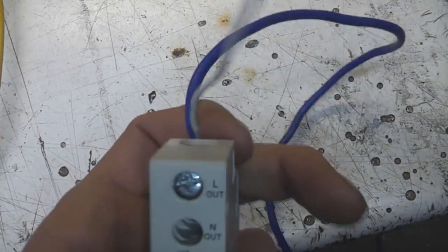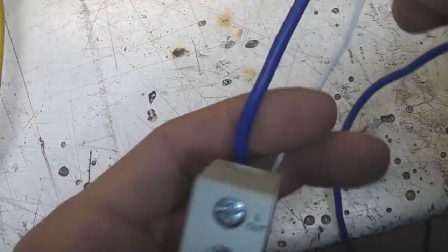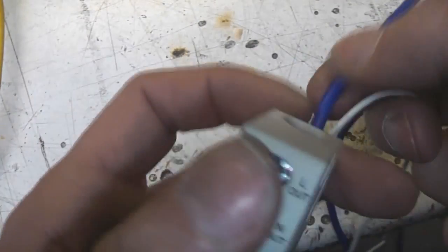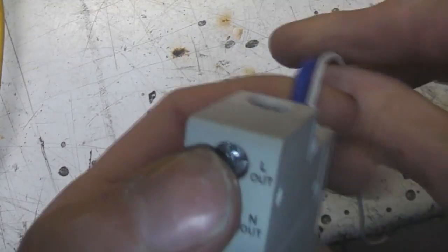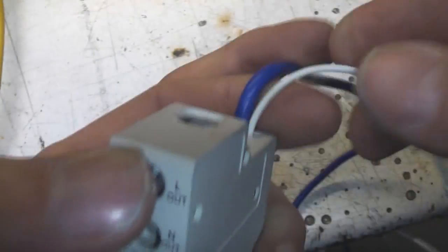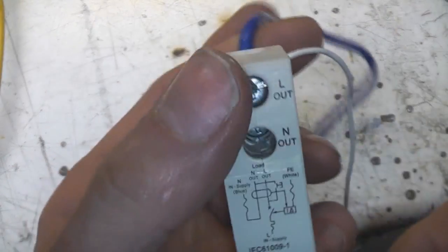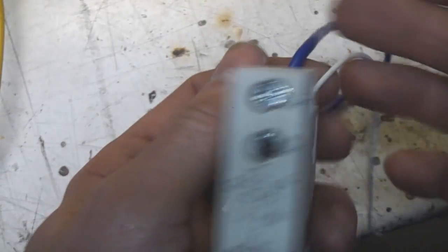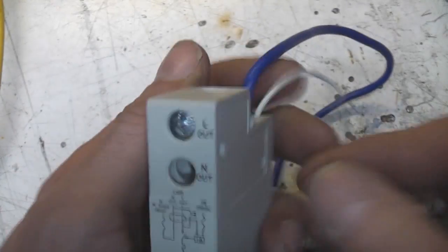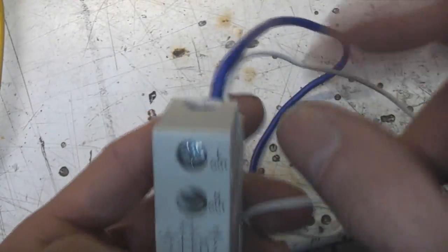Now they don't all have these. The purpose of that is mostly so that the RCD protection will still work in the case of a neutral fault. From what I can gather, it's a little bit unclear as to whether the standard requires it, or whether it depends on the hardware. I'm not entirely sure, but there's also the aspect that the coincidence of a neutral fault and an RCD fault is maybe fairly unlikely. So that's something they don't all seem to have, and so we'll take a look inside and maybe see if we can figure out how this is actually connected and how it works.